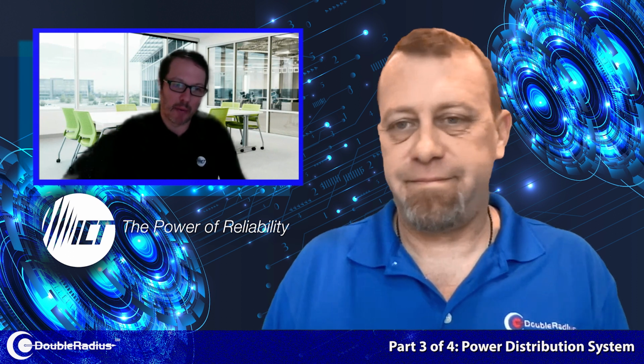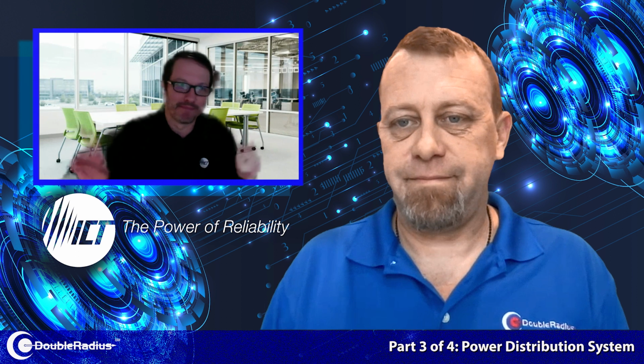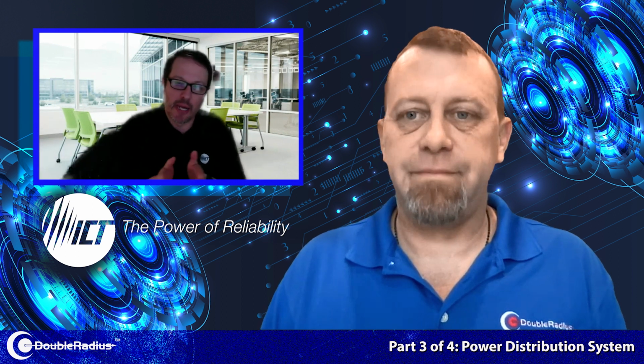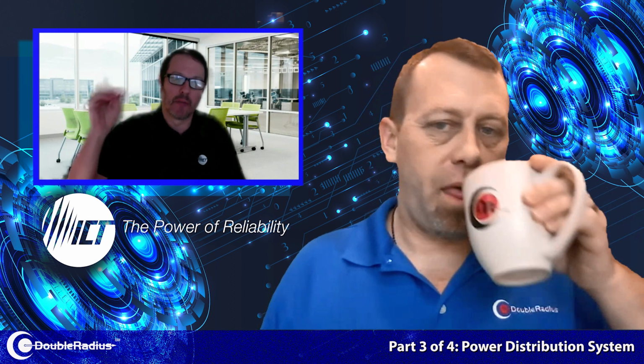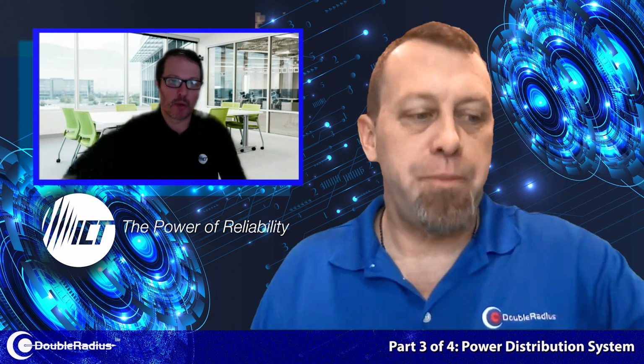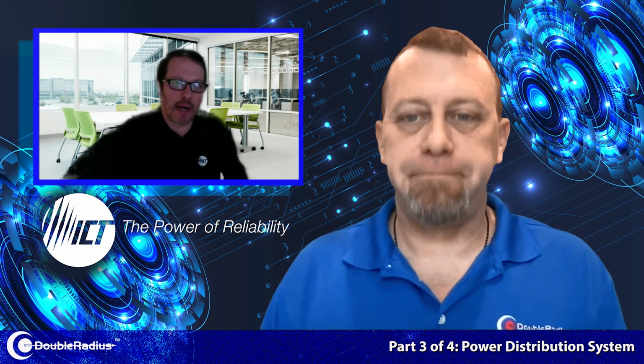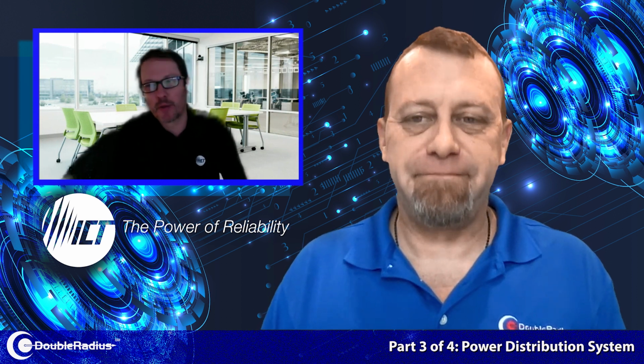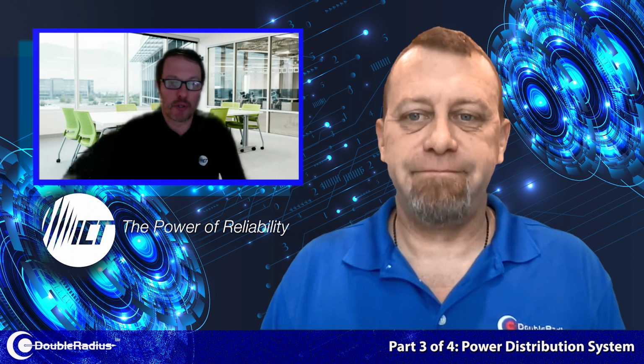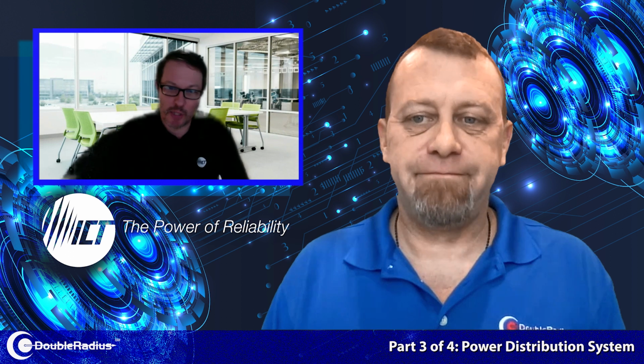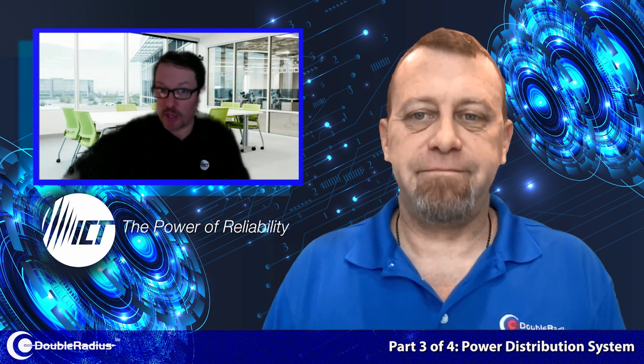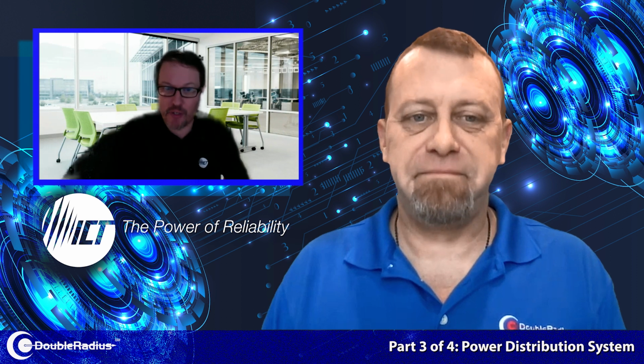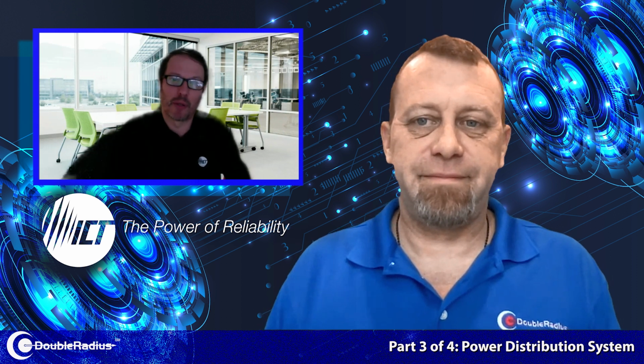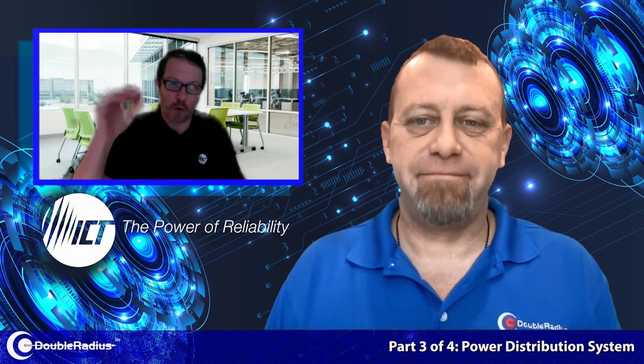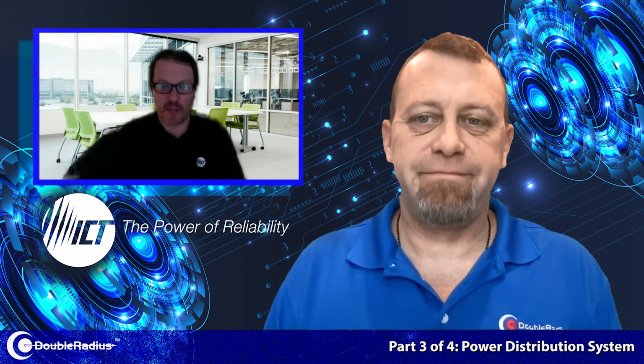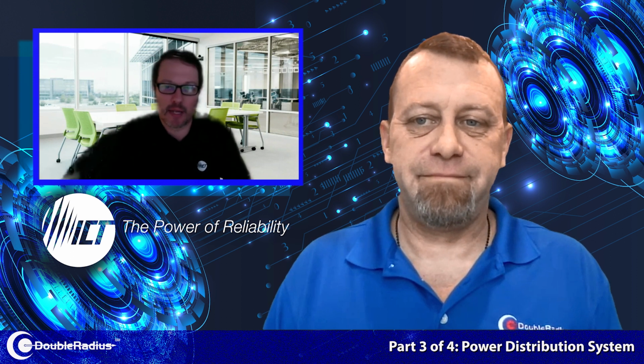We do have the ability with our panels to have what we call, quote unquote, an e-fuse or electronic fuse, in the sense that you can set a current limit for each of the individual output channels. So, for example, you may have a 6 amp load, and you can set a current limit of 8 amps and have a 10 amp breaker in there. If the 8 amps is ever exceeded, we can choose to send you an email alarm to say you have an overcurrent situation on that channel, or shut that channel down and turn that device off as a protection feature. And then you can reboot that remotely. So that's a nice thing. We have a software version of a fuse or breaker, and then we have the physical breaker that needs to be physically reset by a person.